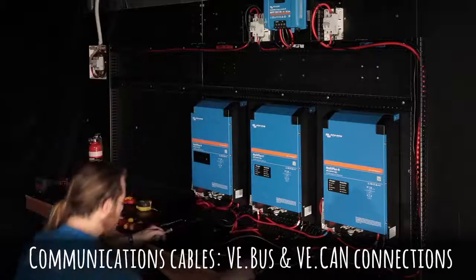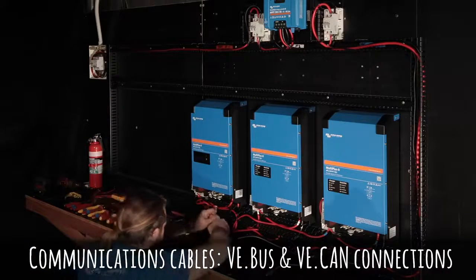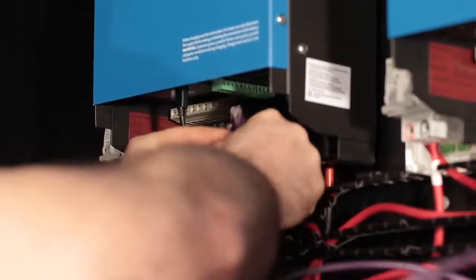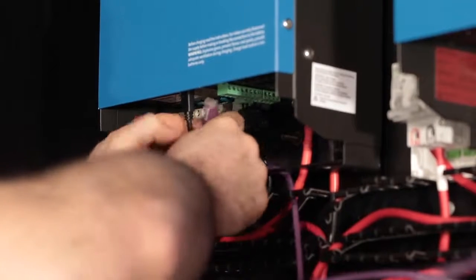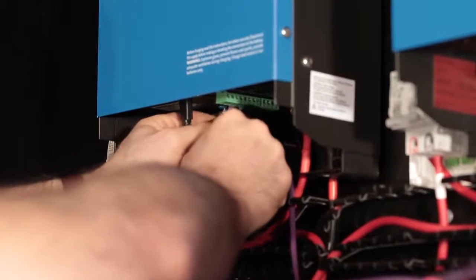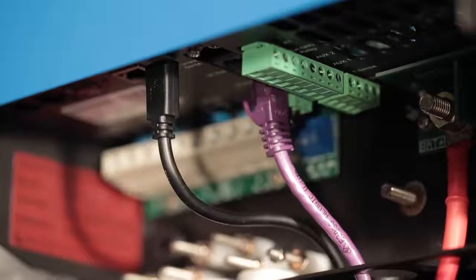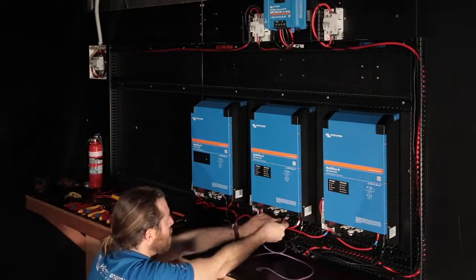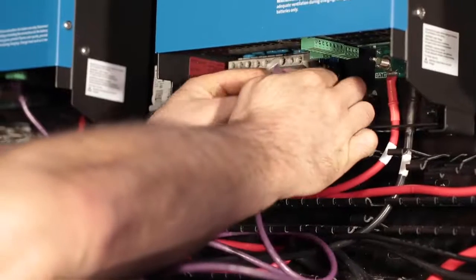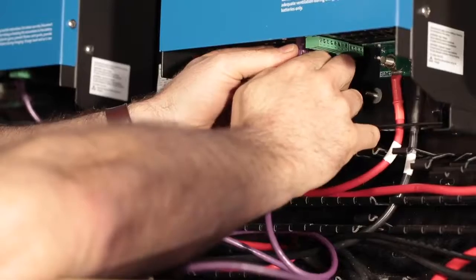Now we've tested the voltage and polarity and we've got our power cable connections in place, we can move to the communications cables. We're going to connect each of the Multi-Plus 2s together through the VE.Bus ports. This is done with the standard RJ45 Cat5 cable. Victron can supply this in various lengths when you're buying your equipment. We highly recommend using manufactured cables. Don't try and make your own cables for this. This communications cable is critically important for the functioning of the system and can cause errors if it's not done properly.